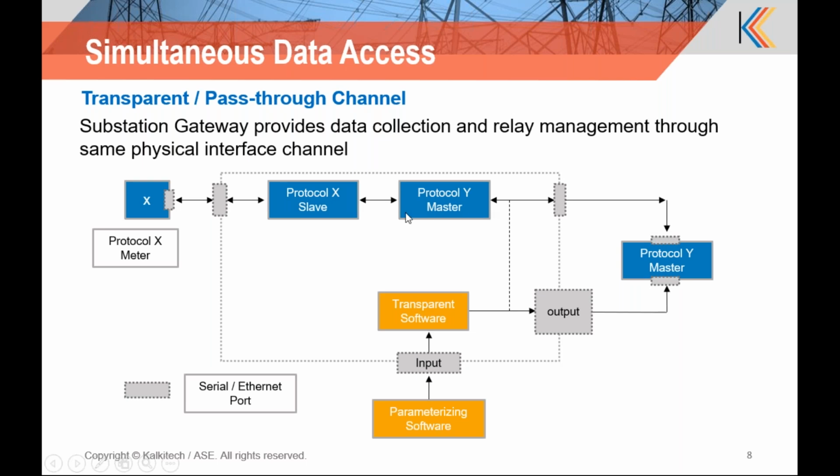And another is the cycle stealing method, in which the master protocol communicates and sends a packet, and in between, when there is data, this data is sent through the same channel over the protocol port, and the reply is sent to the transparent channel too. So one message from the protocol master and a reply to that, and another message from the parameterization tool and a reply to that, like that. It is functioning in the cycle stealing method.